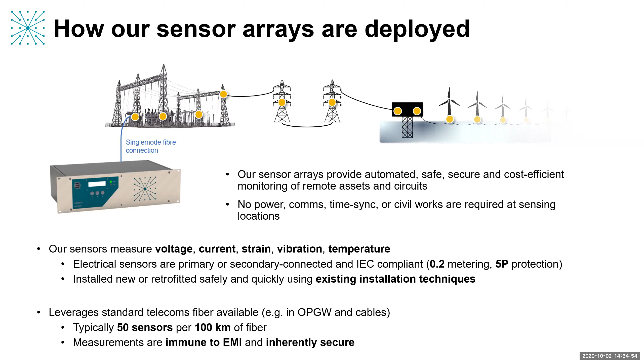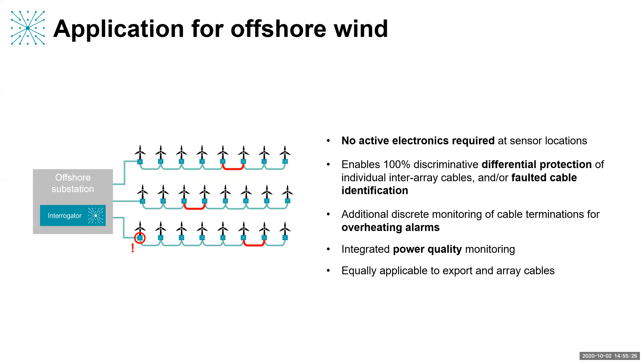So how is this applied to offshore wind? As this slide shows, one or more of our systems can monitor every turbine in a wind farm, looking at multiple different parameters - voltage, current, or mechanical. We can rapidly respond to electrical faults and identify faulted cable sections - it's very trivial, basically. We can provide things like thermal alarms for the cables, and we automatically provide power quality analysis of all our electrical measurements. That's built in at the individual turbine level.